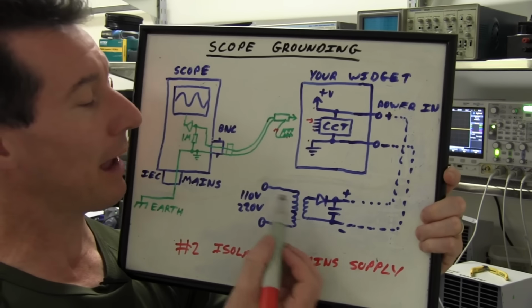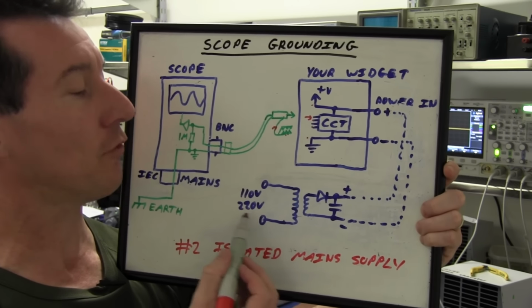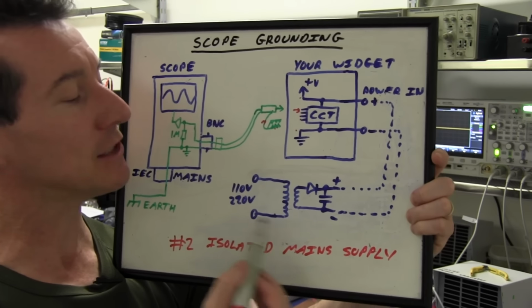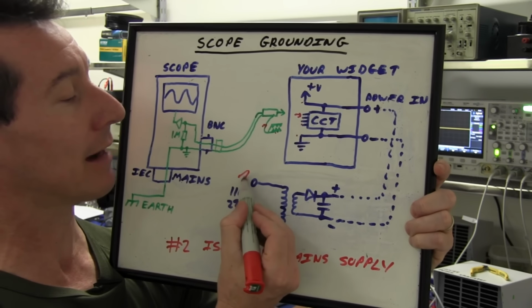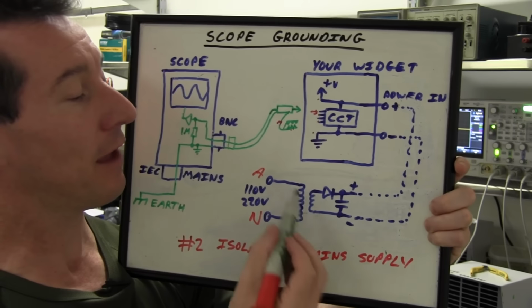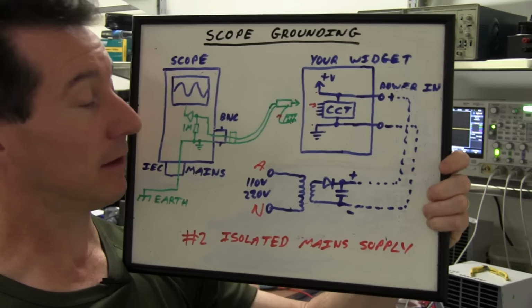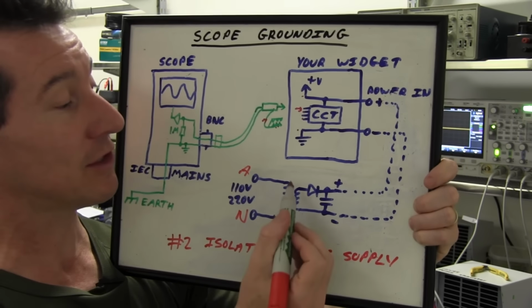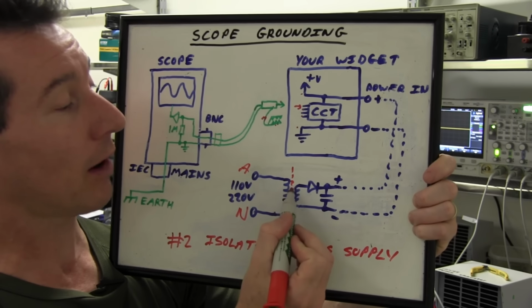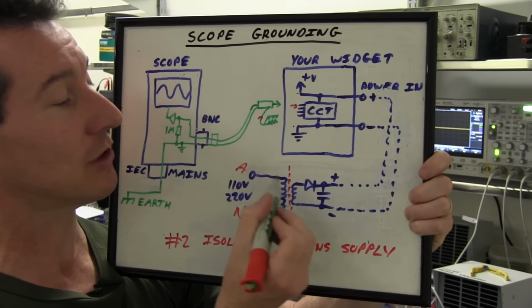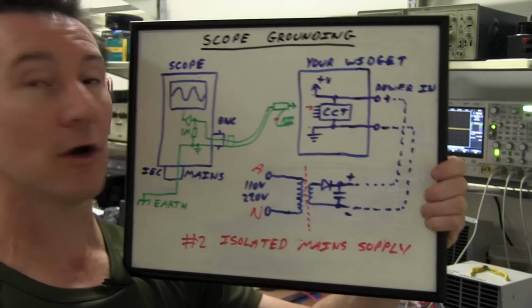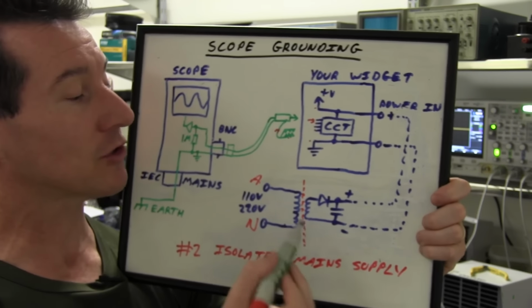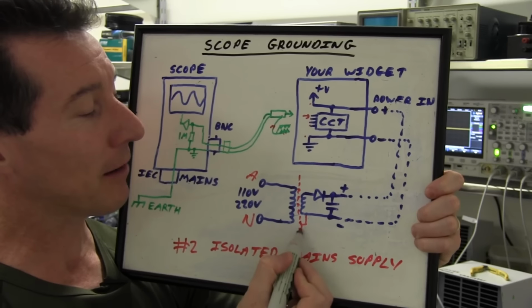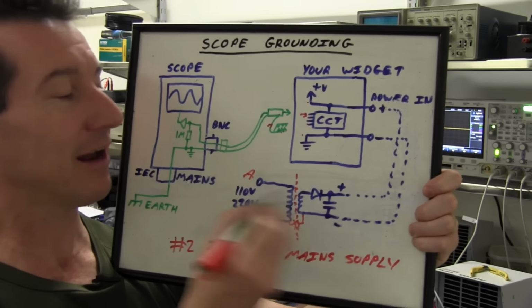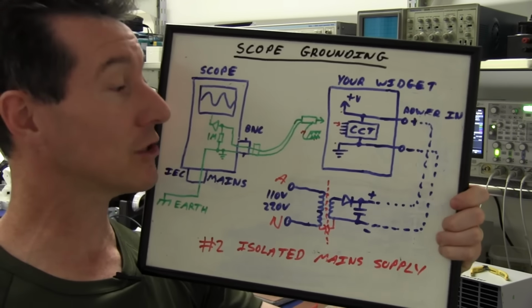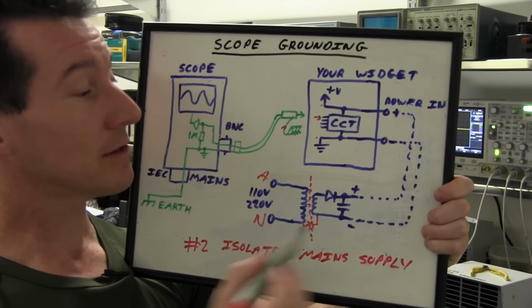All right, let's look at scenario number 2, where we've got one of these isolated mains supplies or a plug pack. We've got our 110 or 240 volt mains coming in here, and there's no earth pin. We've only got our active and our neutral there, and we've got an isolation transformer, 50, 60 hertz, and there's physical isolation, electrical isolation between the primary and the secondary windings. So there's no direct electrical path. There's just a little bit of capacitance, really, but there's no direct electrical connection. So it's an isolated supply.